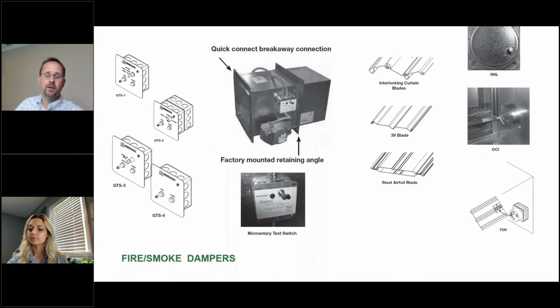There's temperature link override. So if you have a smoke control system, you can provide that, so that they can override that damper if it gets activated for some other reason. And then there's open/close indicators if you have a fire command panel, so it can communicate back the position of each of those dampers.